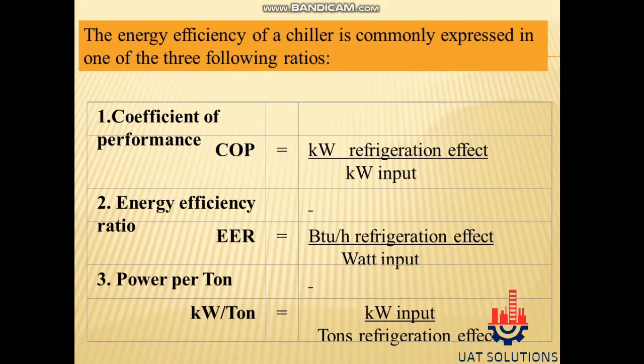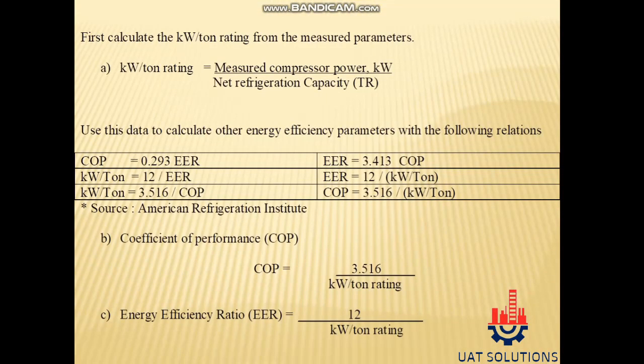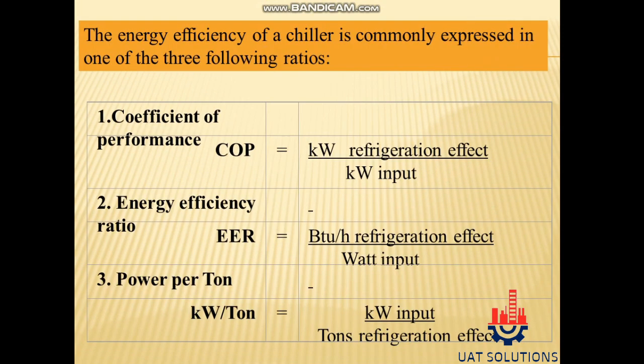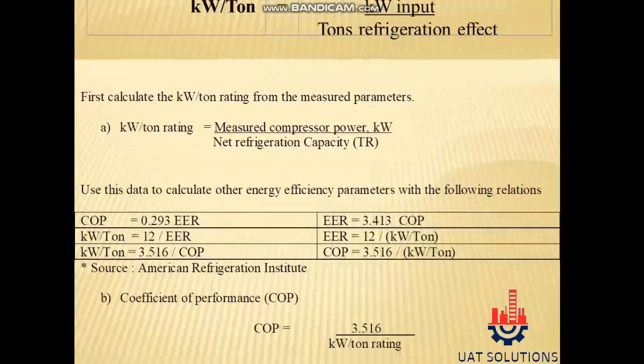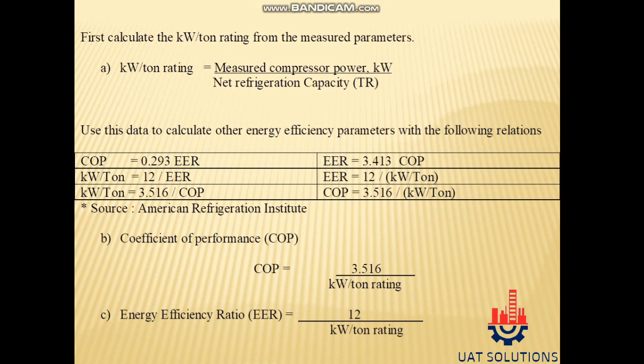The energy efficiency of a chiller is commonly expressed in one of the following three ratios: (1) Coefficient of performance (COP) equals kW of refrigeration effect divided by kW input. (2) Energy efficiency ratio (EER) equals BTU per hour refrigeration effect divided by watt input. (3) Power per ton (kW per ton) equals kW input divided by tons of refrigeration effect. First, calculate the kW/ton rating from the measured parameters: kW per ton rating equals measured compressor power in kW divided by net refrigeration capacity in TR.